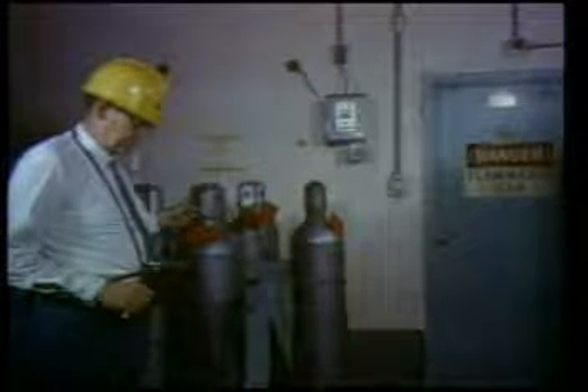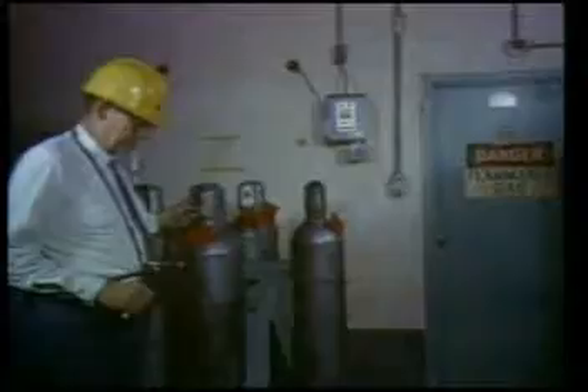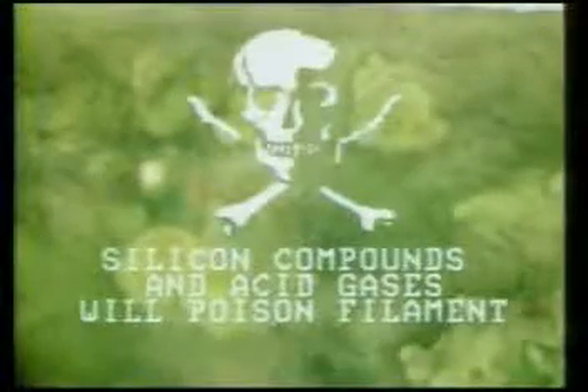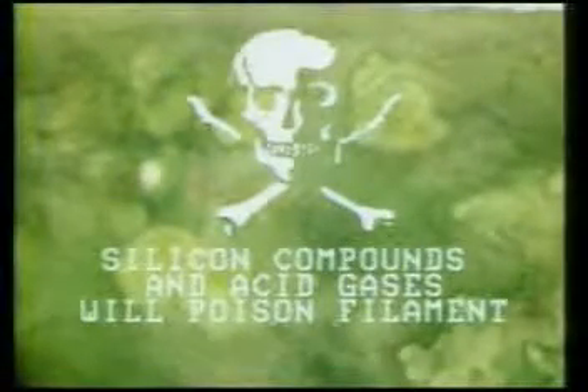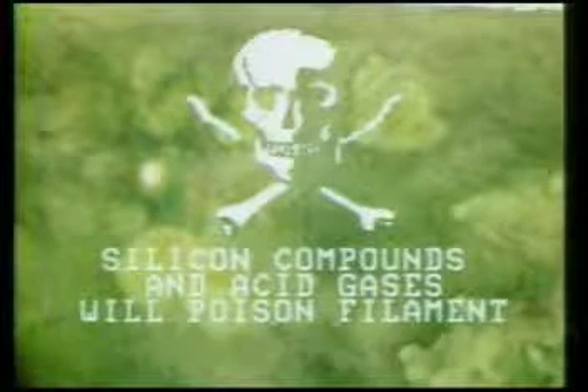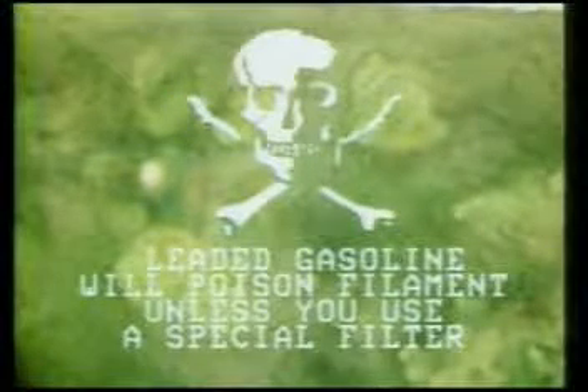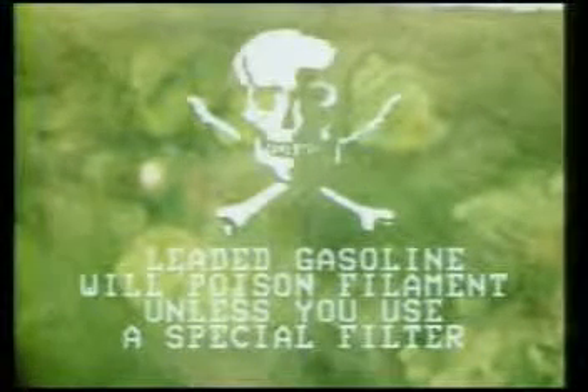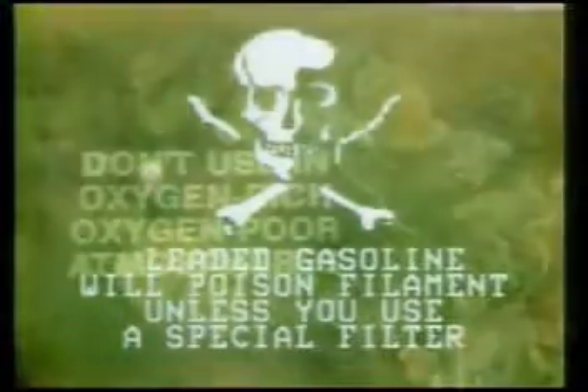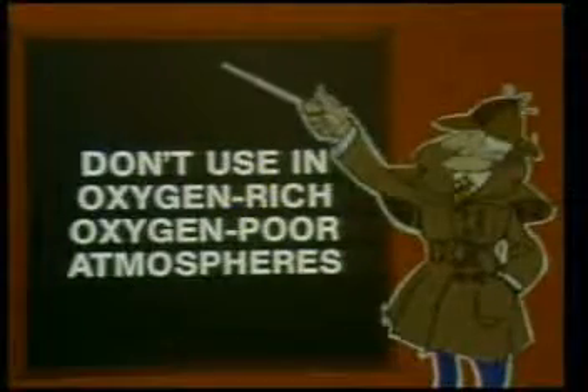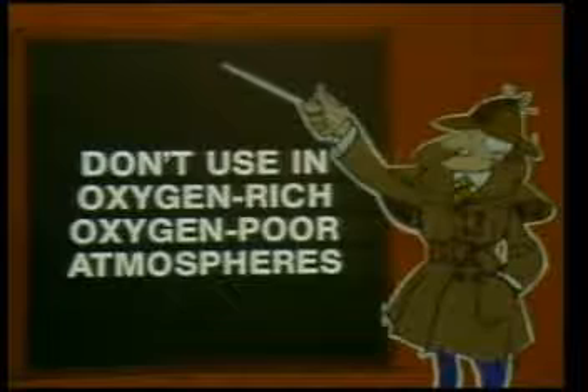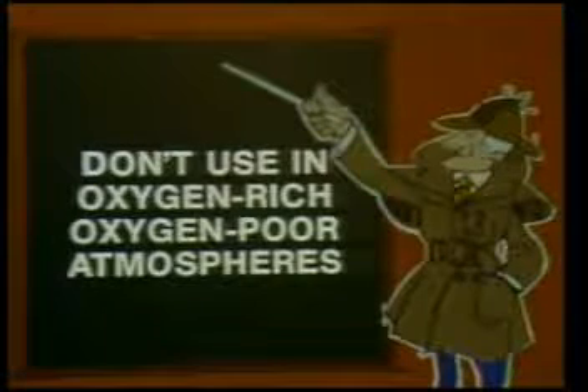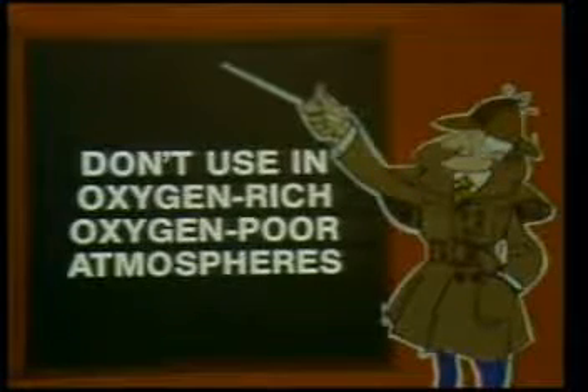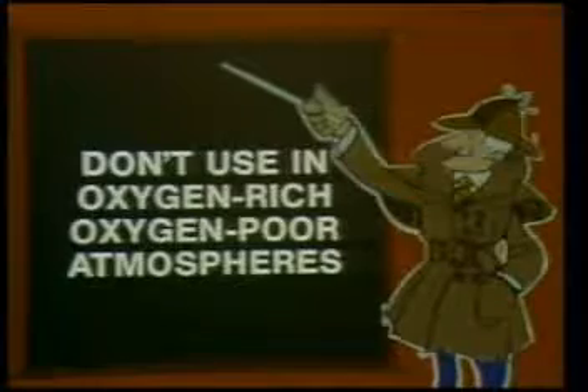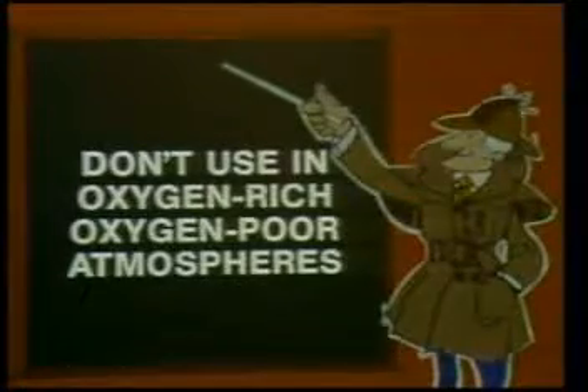The explosimeter Model 2A can't be used under all conditions. For example, silicon compounds and acid gases will poison the filament, and it won't respond accurately. So will gasoline vapors, unless a special filter is used. The explosimeter Model 2A should not be used in oxygen-rich atmospheres where there's more than 21% oxygen. And the Model 2A won't work in oxygen-deficient atmospheres either.